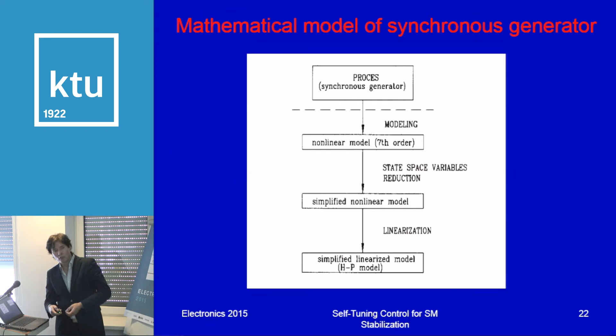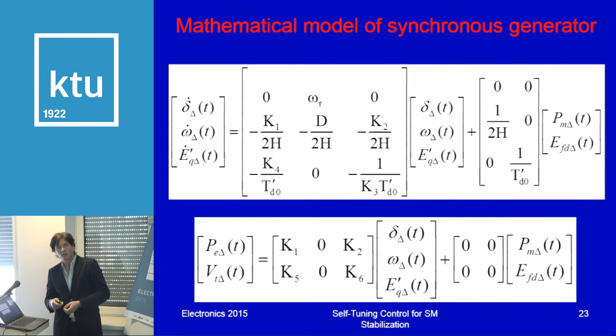This model is simple: two inputs, mechanical torque (or power) and excitation voltage, three state space variables, and outputs. The parameters, which depend on the operating point, are K1 through K6. If we write this model for the nominal operating point we obtain one set of these parameters, but for other operating points we obtain different parameters.